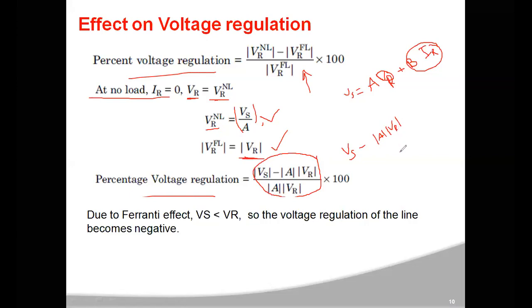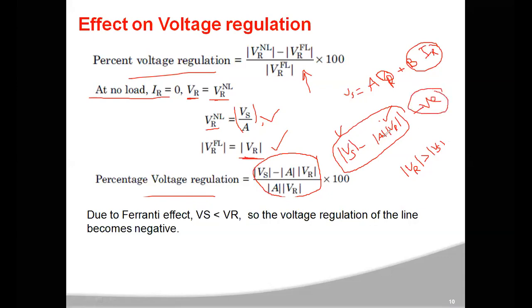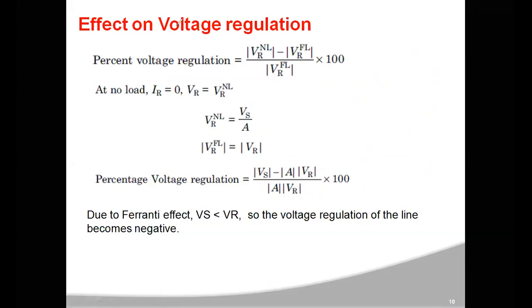If there is a Ferranti effect, the magnitude of VR is greater than the magnitude of VS. That means VS is small compared to A·VR, making the numerator VS − A·VR negative. So when there is a Ferranti effect, the voltage regulation of the transmission line becomes negative. The power factor will also be leading, because there is capacitance domination under no load condition.